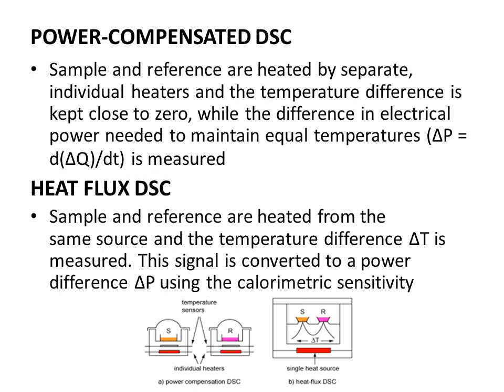The second type is heat flux DSC. In this type, the sample and reference pans are heated from the same single source. The temperature difference, Delta T, is measured and then this signal is converted to a power difference, Delta P, using the calorimetric sensitivity. This conversion can be done manually or automatically by the system.